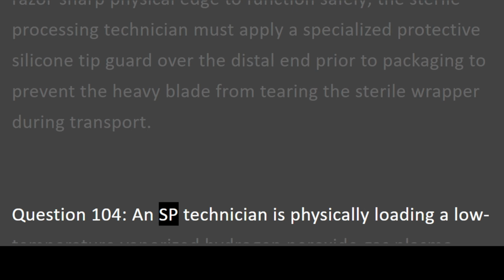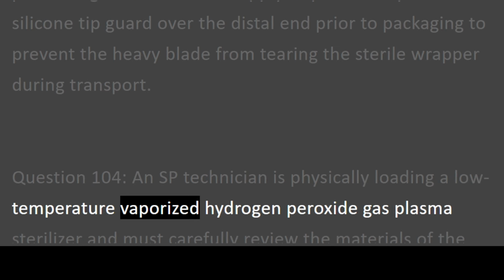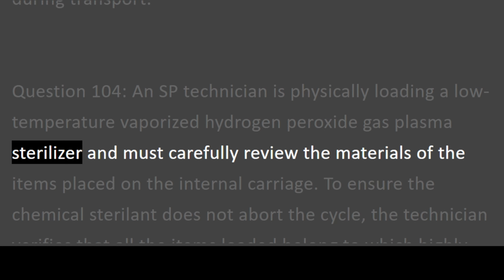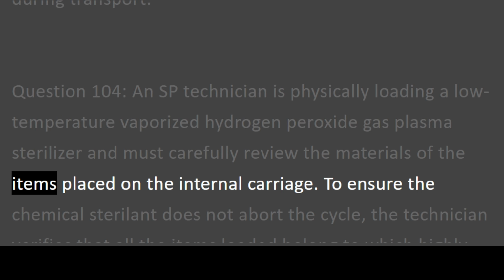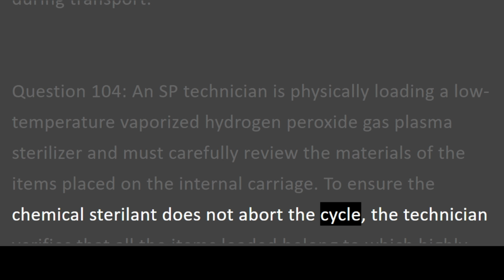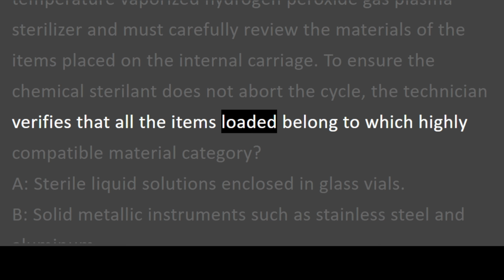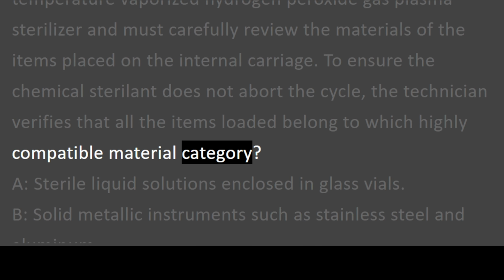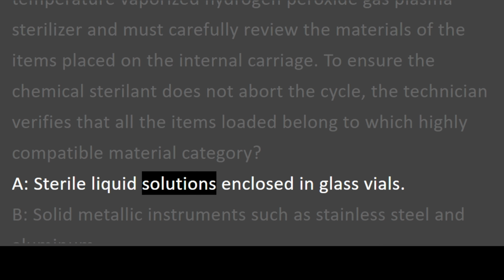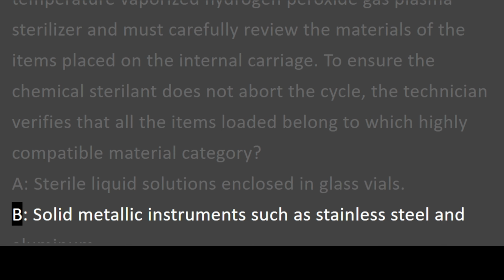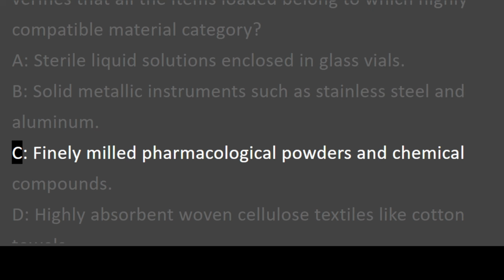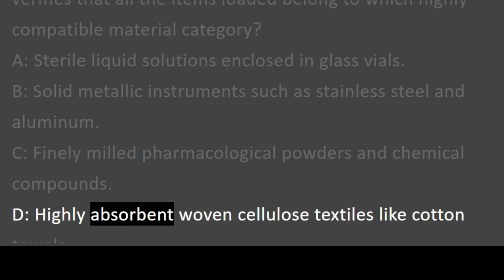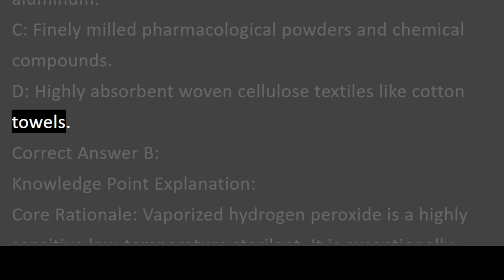Question 104. An SP technician is physically loading a low-temperature vaporized hydrogen peroxide gas plasma sterilizer and must carefully review the materials of the items placed on the internal carriage. To ensure the chemical sterilant does not abort the cycle, the technician verifies that all the items loaded belong to which highly compatible material category? A. Sterile liquid solutions enclosed in glass vials. B. Solid metallic instruments such as stainless steel and aluminum. C. Finely milled pharmacological powders and chemical compounds. D. Highly absorbent woven cellulose textiles like cotton towels.